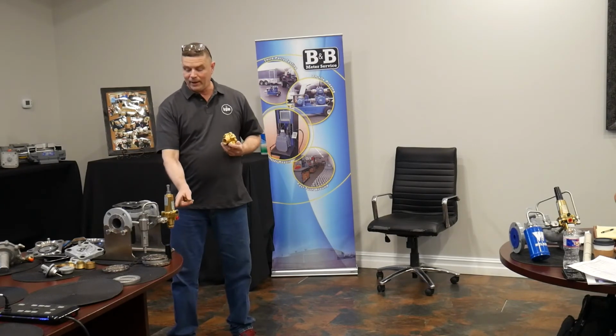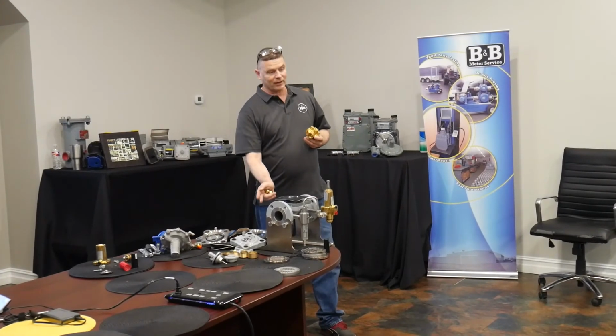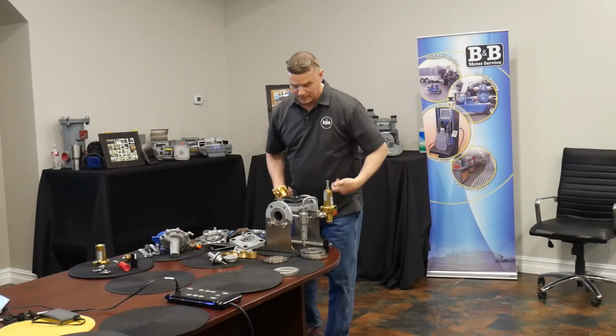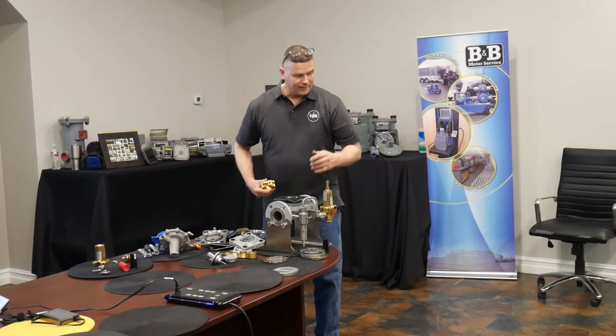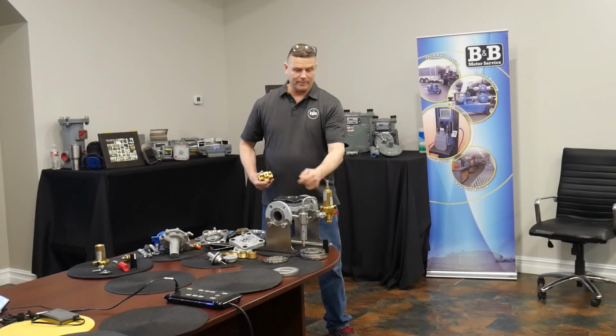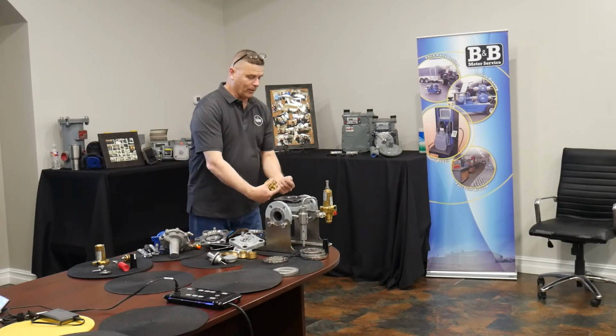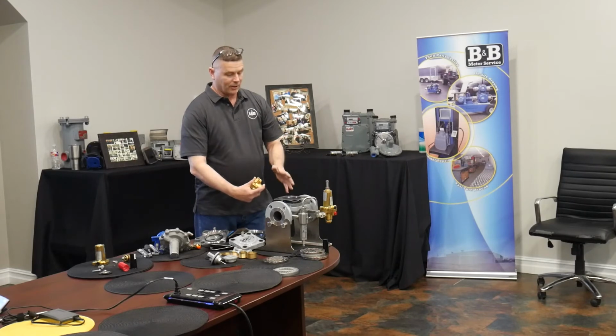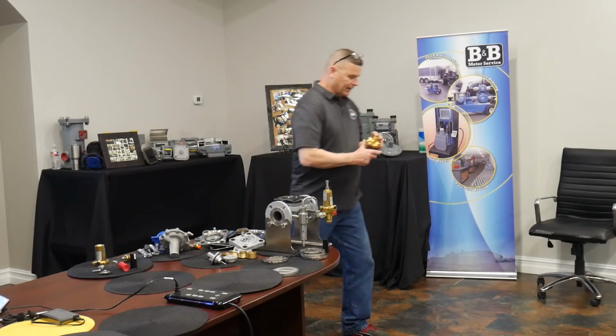That's how, by the way, when I make this for a left-hand run and my pilot's on this side, because I flipped the body around, and this became the place where I mounted the pilot, that's exactly what I'm going to do with the restrictors. I'm going to put it in a pilot that's sitting right here, and it's going to be into the loading port with the inlet loaded on top. So that's how I mirror image it, because it gives me the ability to do that. It doesn't care. All right.